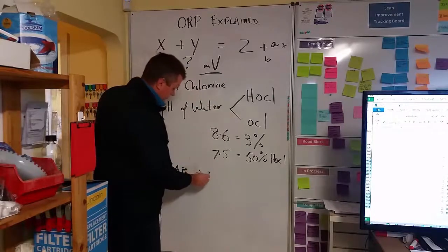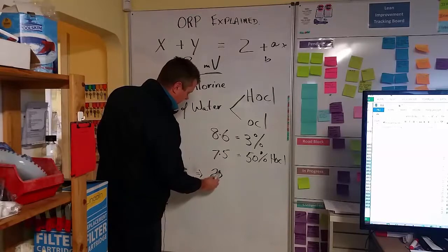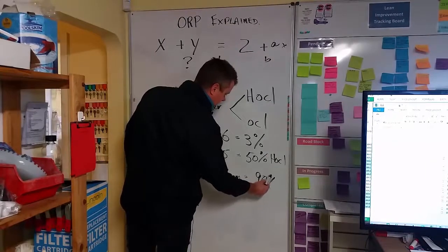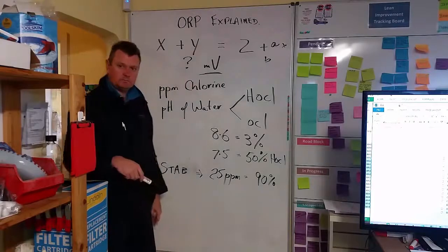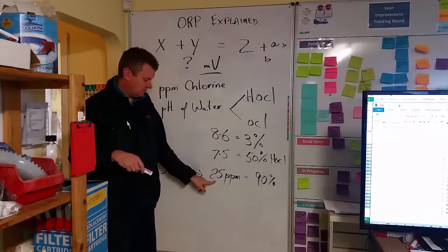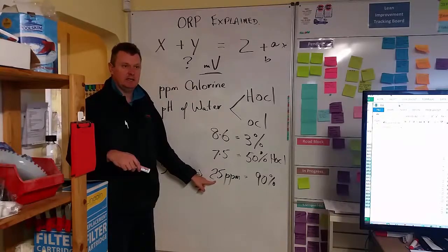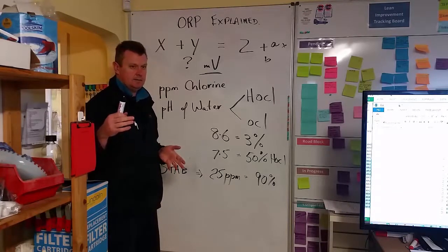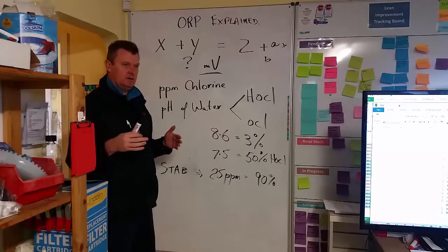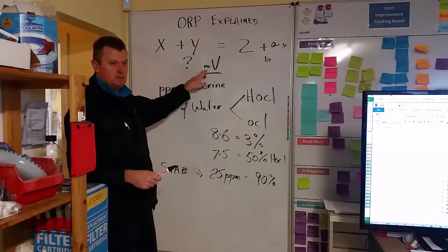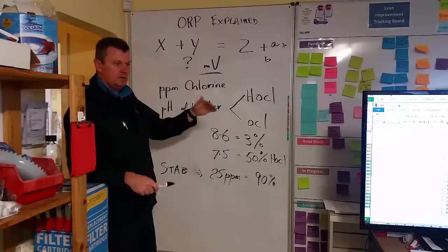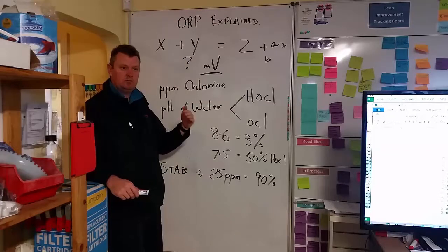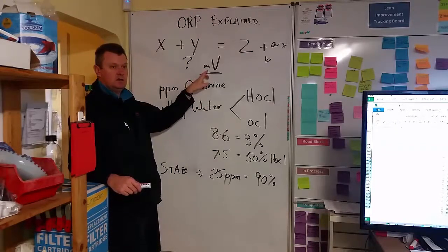So with stabiliser, another thing you might not be aware of, 25 ppm stabiliser is equal to 90% protection of your chlorine. So the minimum we look at is 30, which is I think 95%. And then 30 to 70, 70 is the maximum. That's still only getting up to 98% protection.